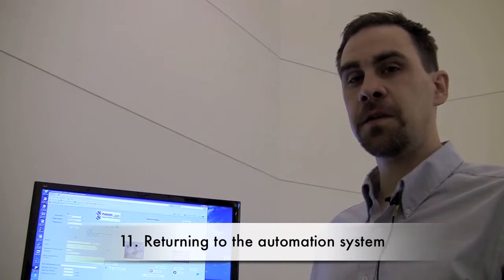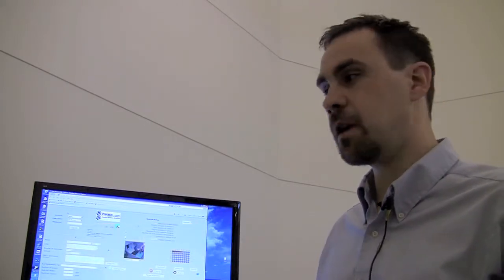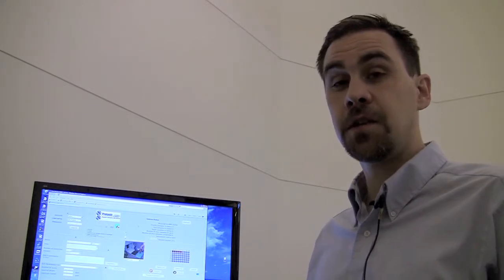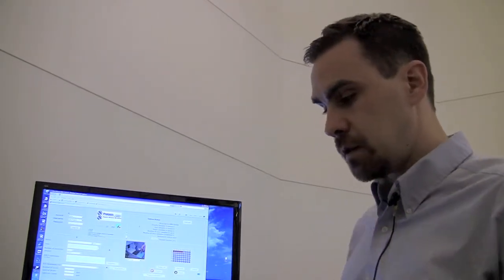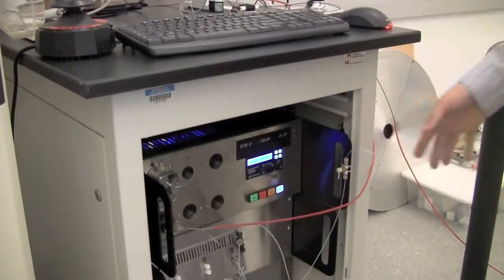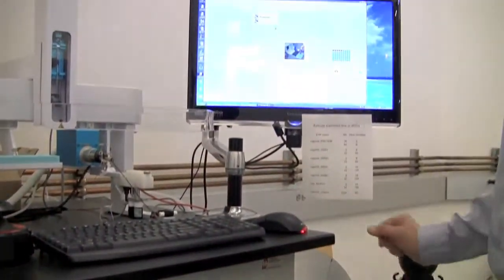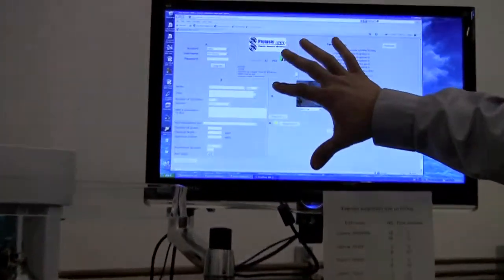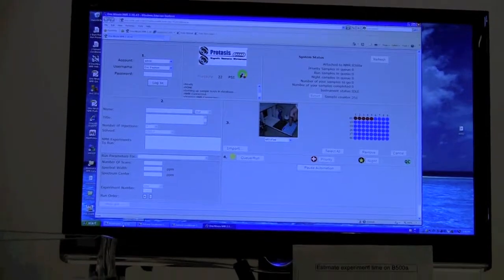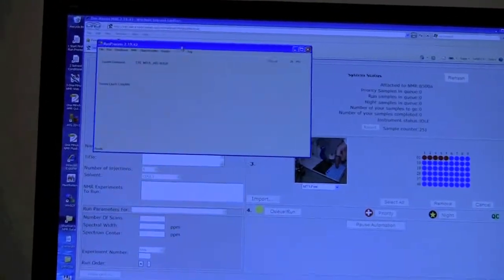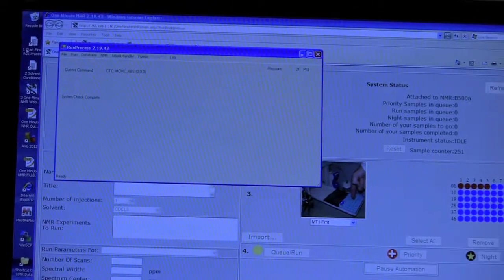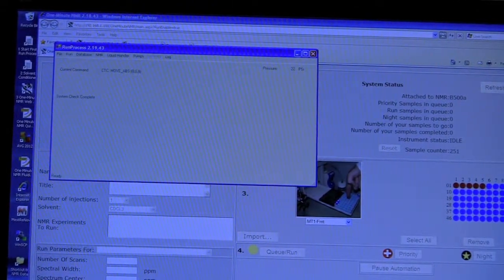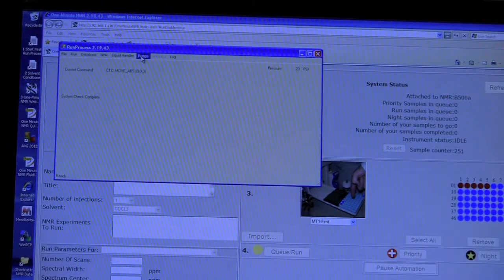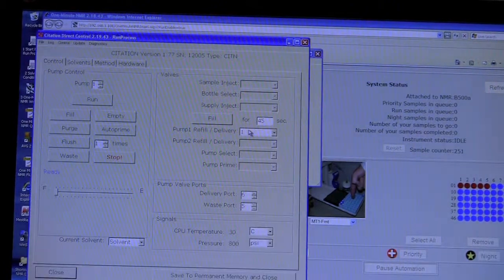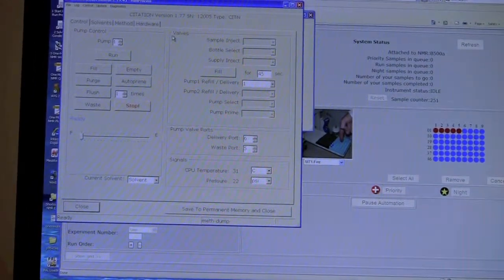Okay, now that we've reconnected the automation system, we need to get it ready for use of the automation system. And the main thing we need to do is flush out the lines using the syringe pump in the automation system with chloroform, or the solvent that's loaded in the automation system. To do that, you can come to the screen here and go to the Run Process window. If this isn't running, you can restart it here with this one Start First Run Process icon, but it should be running already. And then we can go to Pumps, and the HTSL CDCL3 is the option that we want to choose here, and this will open up direct control over the syringe pump.